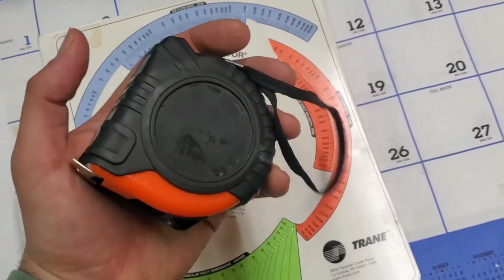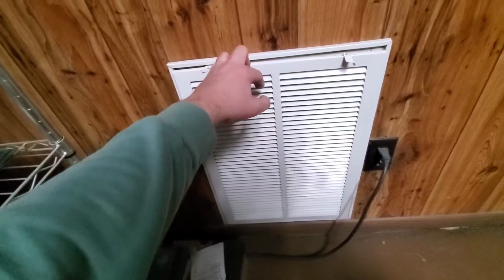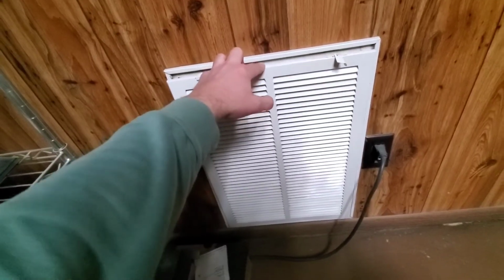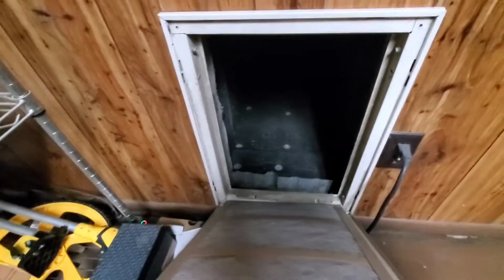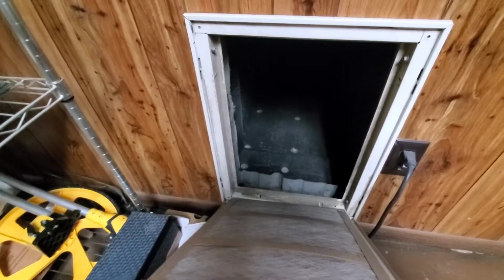Let me give you guys some more tips. All right, say you can't get to your ductwork, but you've got a return grill in your house. This is a good way for you to measure and find out what size your return duct is, so that you can figure out if it's sized correctly. You open up the return grill, you get a flashlight, and you find your duct. Of course, this is the duct right here. There may be a round duct though, and you can measure and figure out what size it is. Maybe it's 14, maybe it's 16, but this is a good way for you to measure your ductwork and figure out what size it is.